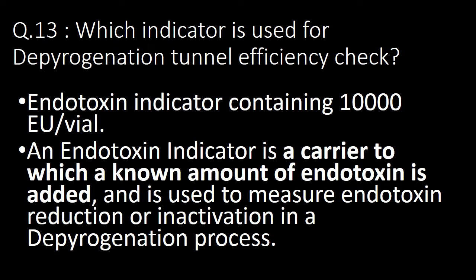The next very frequently asked question: which indicator is used for depyrogenation tunnel efficiency check? An endotoxin indicator containing 10,000 EU per vial is used for depyrogenation tunnel efficiency check. An endotoxin indicator is a carrier to which a known amount of endotoxin is added and is used to measure endotoxin reduction or inactivation in a depyrogenation process.